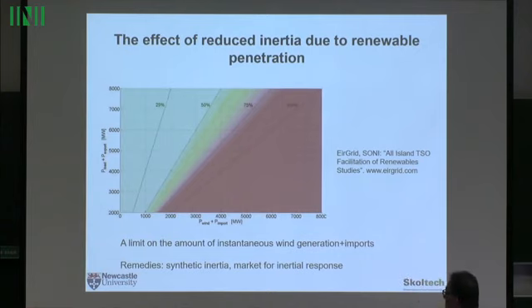This so-called synthetic inertia works because those wind generators are connected by means of power electronics, and with power electronics you can simulate that it behaves like a traditional AC generator. So if frequency drops, it gives more power. A wind turbine is, at the end of the day, a turbine with some inertia, so you can temporarily draw more kinetic energy from it by control means. It will slow down, behaving like a traditional generator. This is referred to as synthetic inertia.